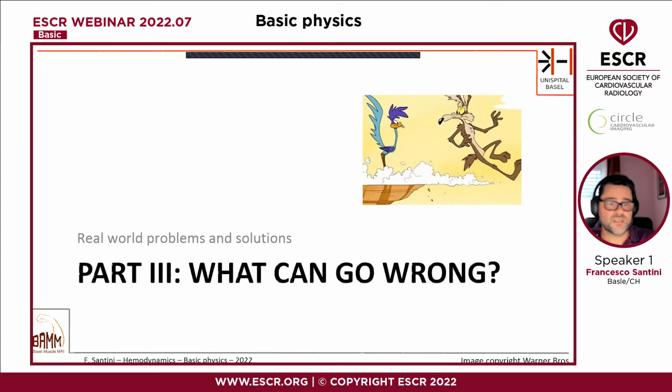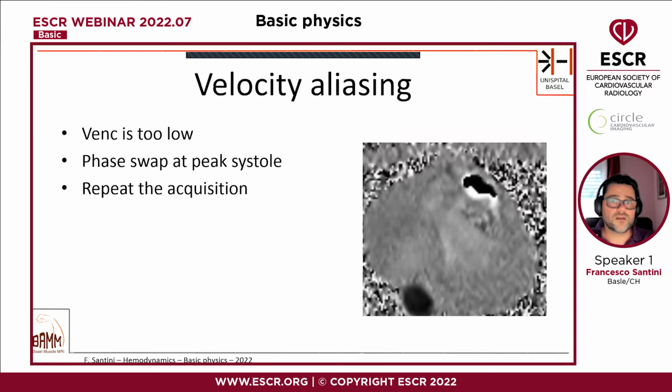I would like to conclude this presentation in a few minutes by also mentioning what can actually go wrong and how we can properly set up a protocol for the velocity acquisition. The first thing that can go wrong is, of course, related to Venc. I had already briefly mentioned it before. And if the Venc is too low, we are in a situation like this. This vessel should be all white because the velocity is coming towards us. But we see there is a large black part that has an abrupt change between white and black. This means that the phase here overflowed. It went from a plus 180 phase to a minus 180 phase.